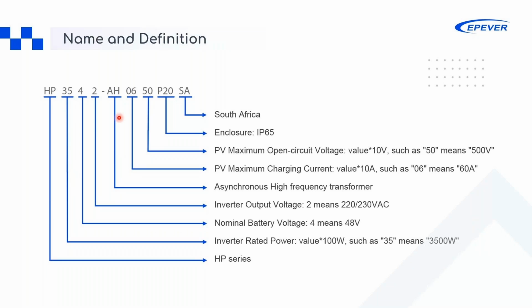06 refers to the PV maximum charging current multiplied by 10, so 06 means a charging current of 60 amps. Then 50 indicates the PV maximum open-circuit voltage multiplied by 10, meaning this unit can handle up to 500 volts of DC from the PV input. P20 refers to the ingress protection rating, and finally SA relates to the specific region this product is designed for—in this case, South Africa.